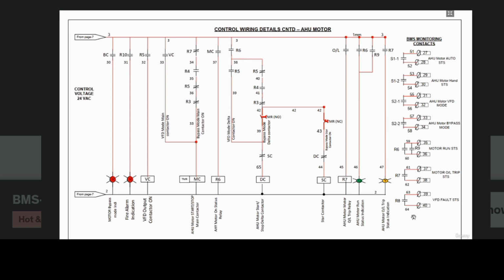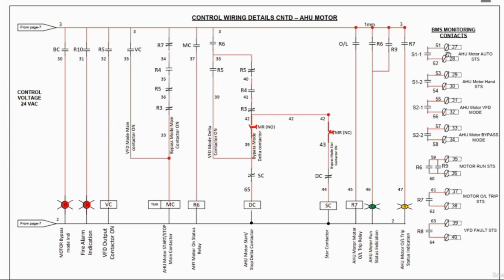Here we have the monitoring terminals where we shall connect our cables for the BMS. First of all, we have the status of the selector switch, which is the auto status. It shall be terminated on terminal numbers 27 and 28, and then the hand mode status is available on 29 and 30. Similarly, we have other signals available, like motor run status on terminal numbers 35 and 36. In this way, by reading the MCC drawing, you can know where you shall terminate your BMS cables.